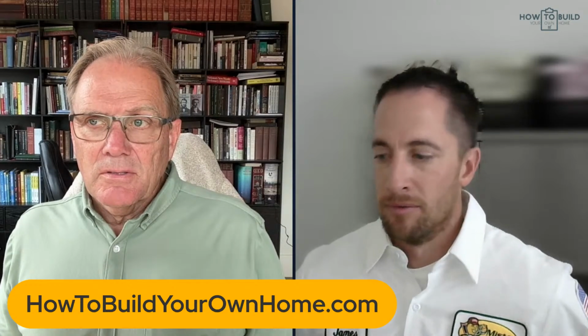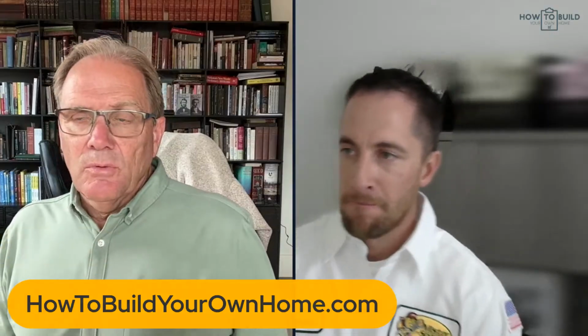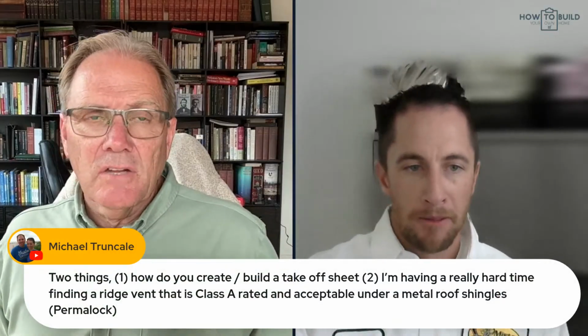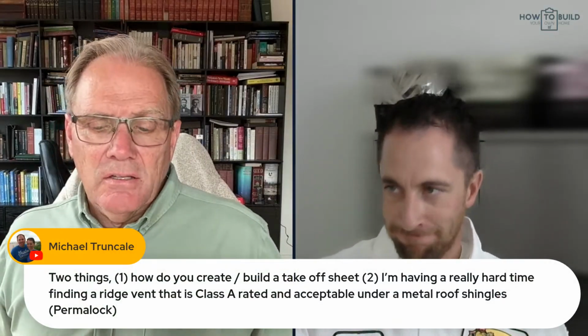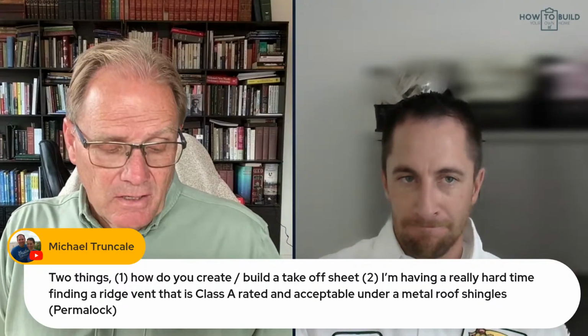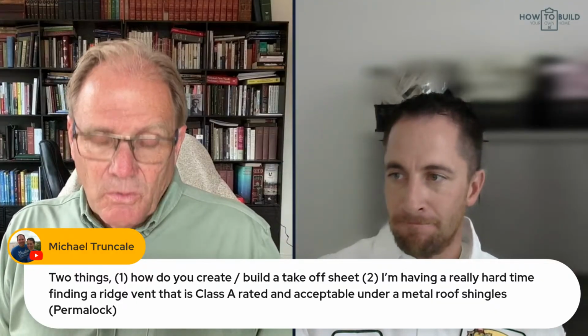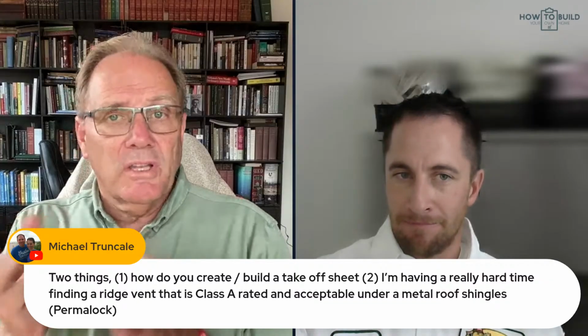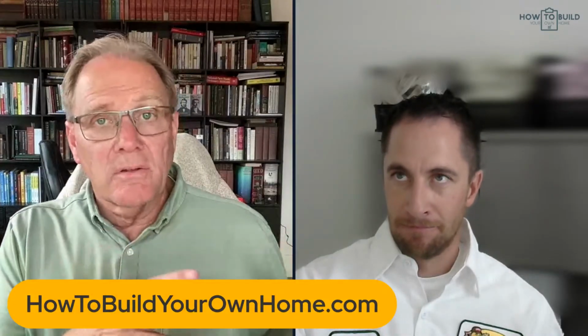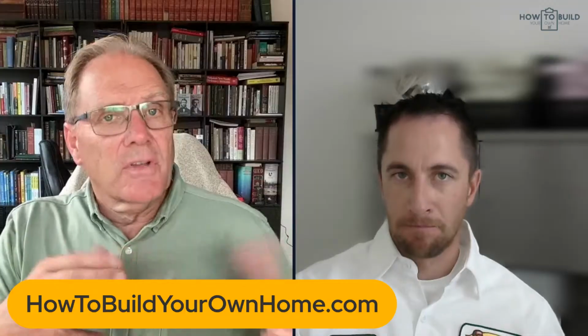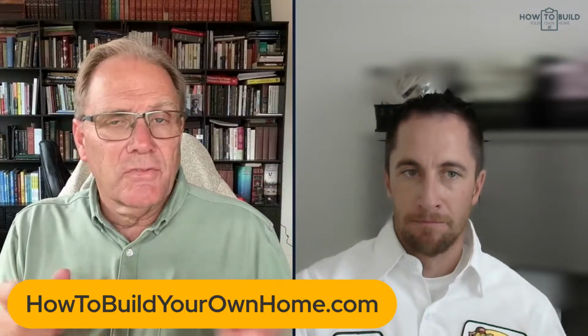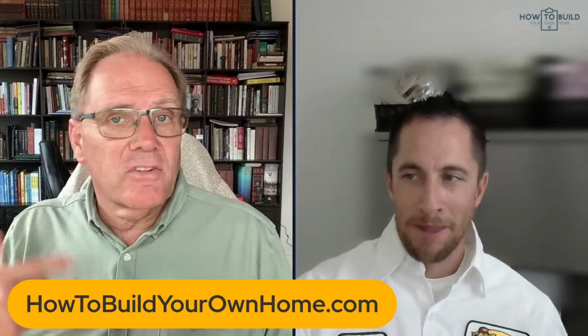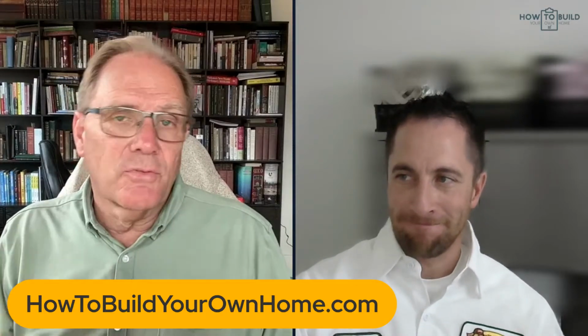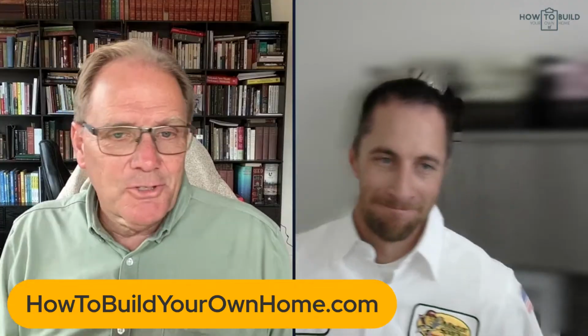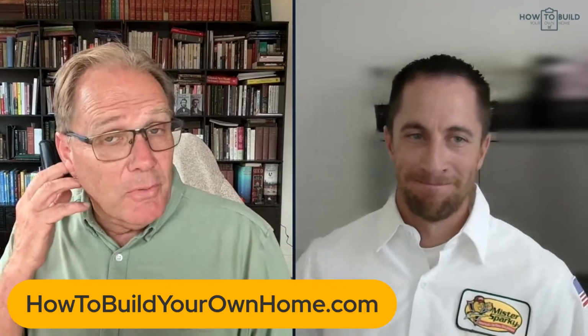Let's take some questions real quick, but I want to emphasize this one thing. I've seen a lot of track home builders, especially back in the day, and I still see it every once in a while, where they'll take a 14-2 wire, which is the white cable. 12-2 is typically the yellow covering on it; it's thicker, denser, stiffer to use. But they'll wire 2 bedrooms, plugs, lights, everything on one circuit with a 14-2 wire, and the electrician is grinning because he knows that's going to trip every once in a while.